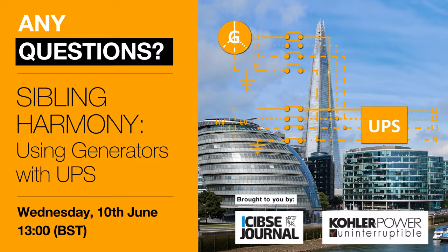Another big consideration with any motor load is, is it regenerative? If we're going to have a regenerative load, we're going to be backfeeding the UPS, and the UPS has to be specifically designed for those installations. But it's something that we do quite a lot of for life safety, to use the UPS in those situations. But like I said, we have to fully understand the requirements of the load and the customer to make sure we can give the correct solution.